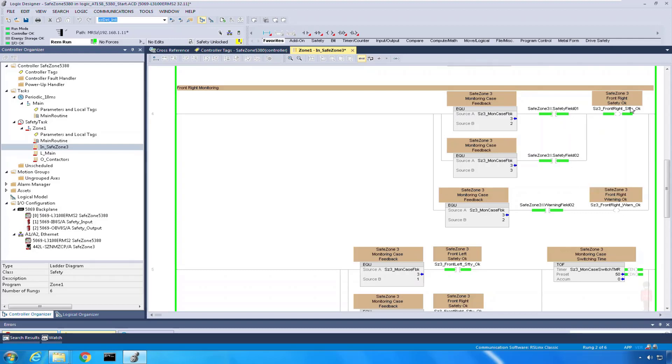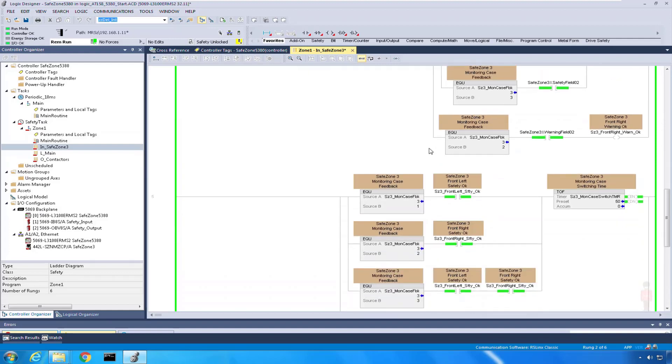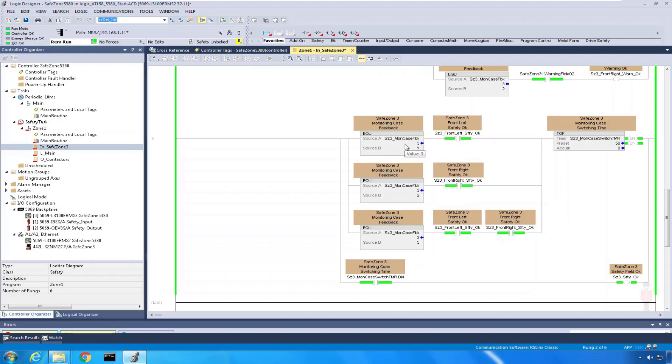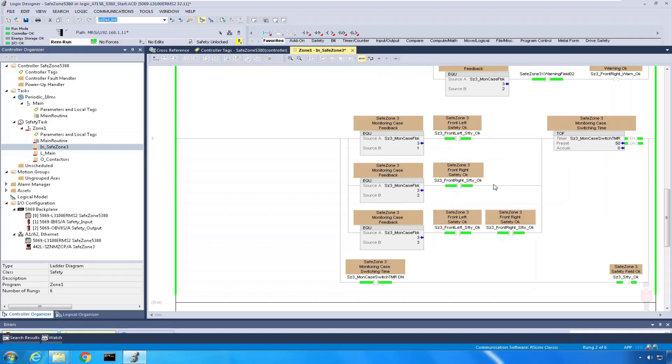The final rung is just really confirming that if I'm in that case and I am getting that okay. As I'm case switching, you can look up in the user manual about switching time. When I go from monitoring case 1 to 2 to 3, there's going to be a little bit of time because the scanner needs to double-check. It needs to switch to determine whether that newly monitored field set is actually safe. In my application, I trended it and it's about a little less than 50 milliseconds because I turned all my adjustments down quite low.